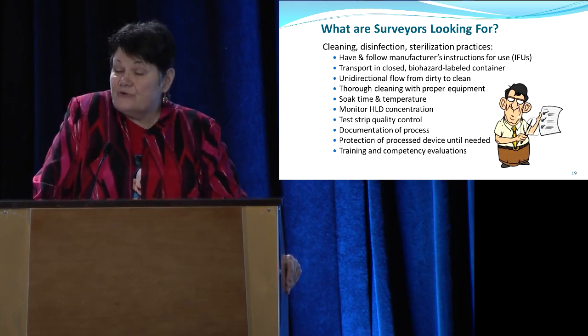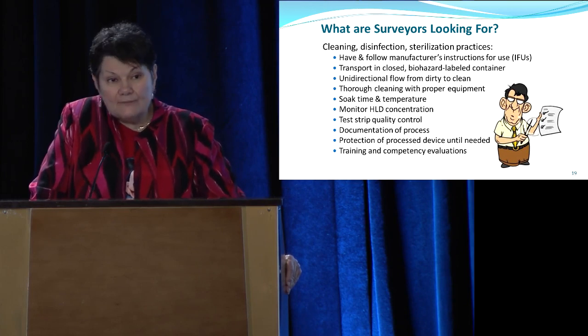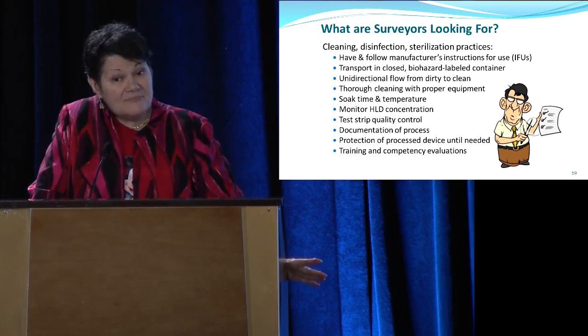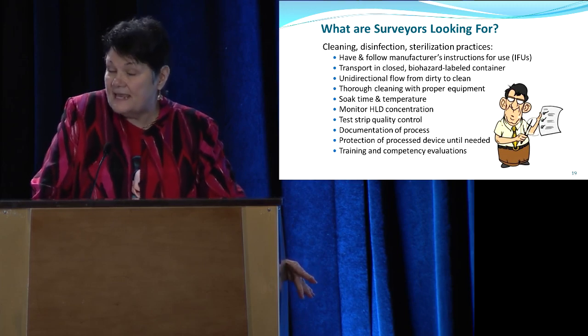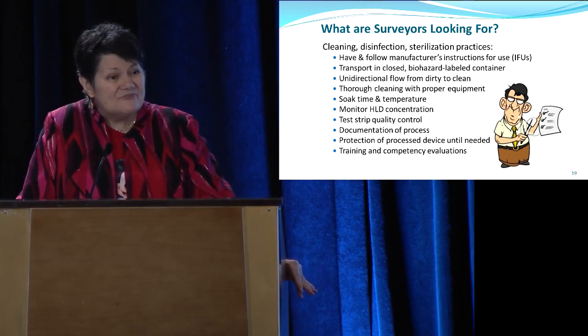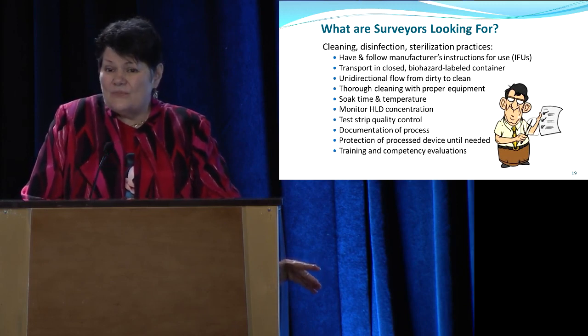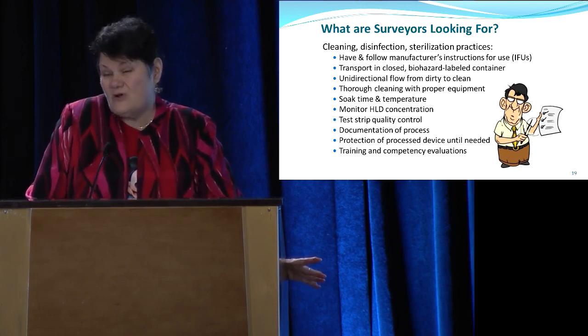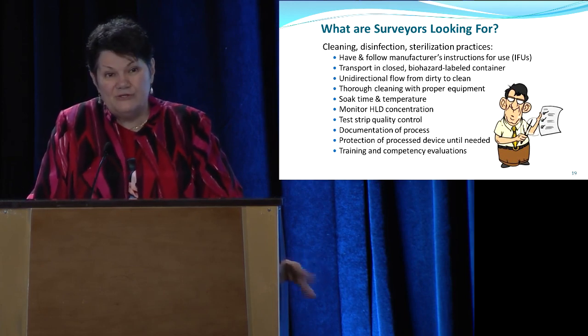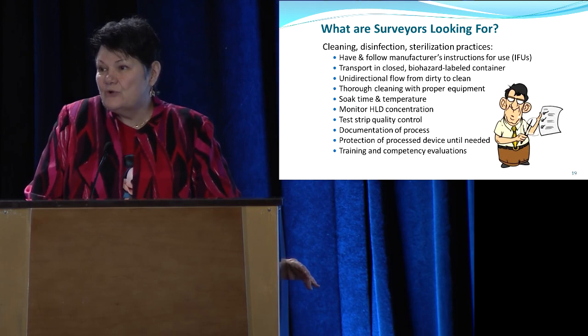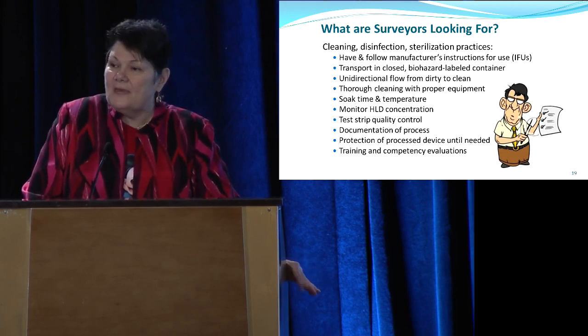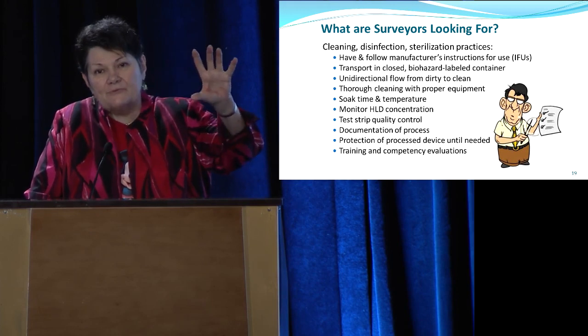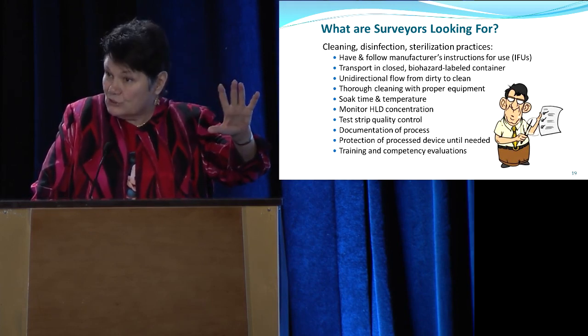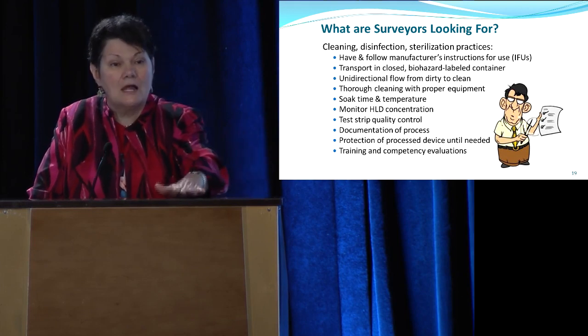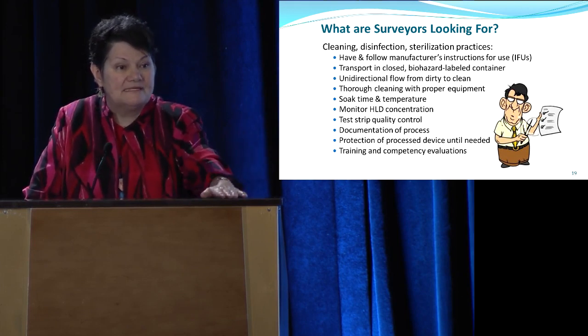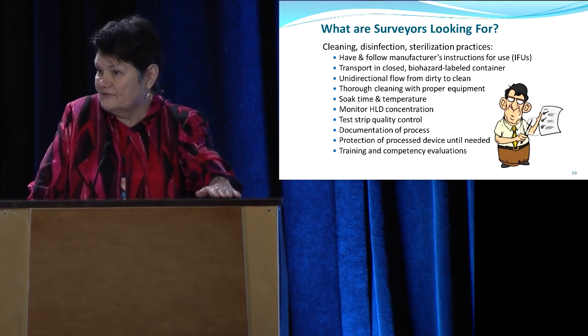Soak time and temperature for high-level disinfection. You need to have a timer, you need to have a thermometer, because some of the high-level disinfectants say 12 minutes, but it's 77 degrees Fahrenheit, and you know, that may not be the temperature and probably is not the temperature on the counter in your cleaning area. So you would then need to increase the soak time, and if there isn't a table in the written instructions, I would contact the manufacturer and ask for those instructions. Okay, our average temperature is 69 degrees. How many minutes does that translate into for high-level disinfection?